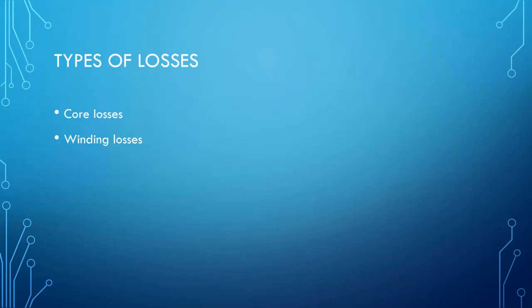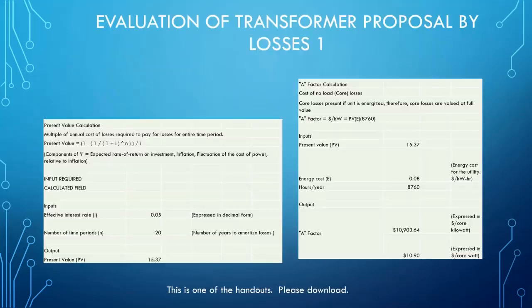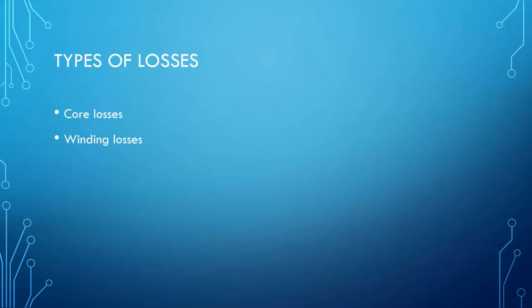There are two types of losses in a transformer. We have to talk about the core losses and winding losses. I'm going to go back to the slide for a second before we get into the actual evaluation. The core losses are what we call no load losses. They're the losses that are required to energize the transformer. So they're either on or off. It's not dependent on current or voltage or anything else. When the transformer becomes energized and the core is magnetized, those losses are present, regardless of how much current is going through it.